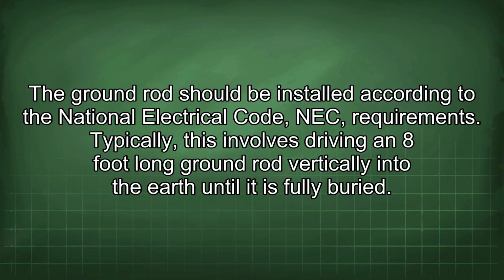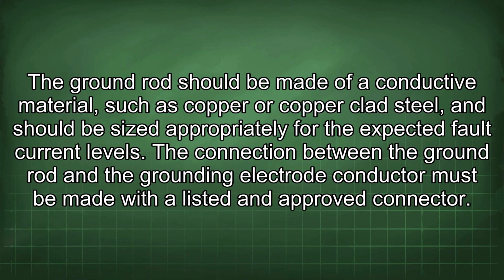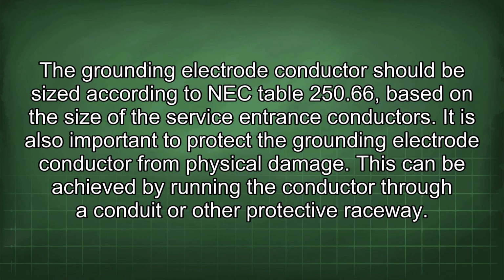Typically, this involves driving an 8-foot-long ground rod vertically into the earth until it is fully buried. The ground rod should be made of a conductive material, such as copper or copper-clad steel, and should be sized appropriately for the expected fault current levels. The connection between the ground rod and the grounding electrode conductor must be made with a listed and approved connector. The grounding electrode conductor should be sized according to NEC Table 250.66, based on the size of the service entrance conductors.